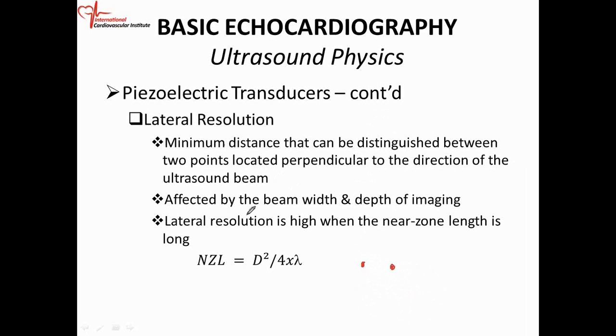Lateral resolution is affected by something we call beam width and the depth of imaging. Okay? So the lateral resolution is high when... this is the formula for lateral resolution. We usually talk about the near zone length. So the lateral resolution is high when the near zone length is long. The higher this number, the better the lateral resolution. It's the near zone length.